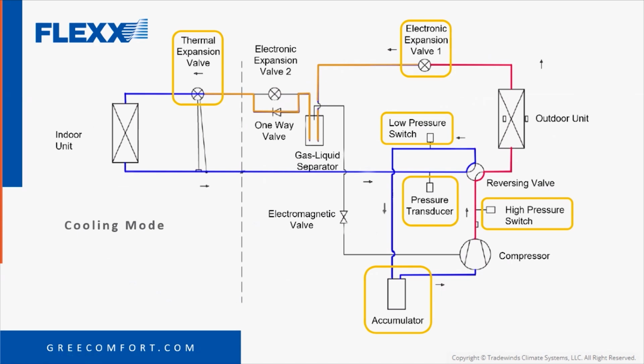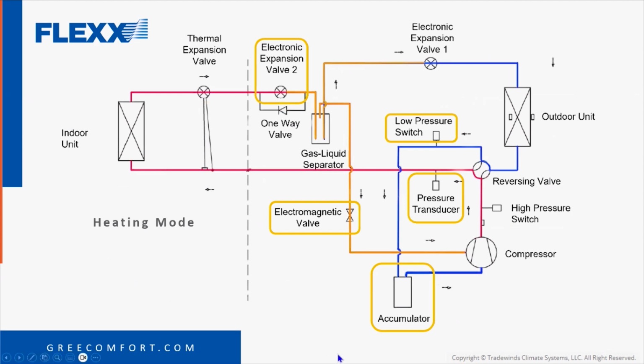So if this is cooling mode, let me go to heating mode. And this is just normal heating mode operation. But if this was in low ambient heating, this gas liquid separator, your liquid's going to be down here on the bottom, so you're not affecting your liquid flow of refrigerant, right? At the top of here is going to be warm refrigerant gas, right? So they pull off of the top of that during low ambient heating. They open the electromagnetic valve and they dump it back into the compressor, compress it again.